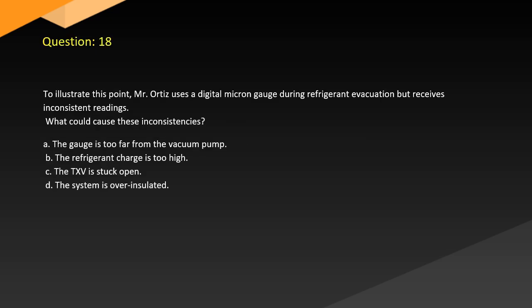Question 18. To illustrate this point, Mr. Ortiz uses a digital micron gauge during refrigerant evacuation but receives inconsistent readings. What could cause these inconsistencies? A. The gauge is too far from the vacuum pump. B. The refrigerant charge is too high. C. The TXV is stuck open. D. The system is over-insulated.